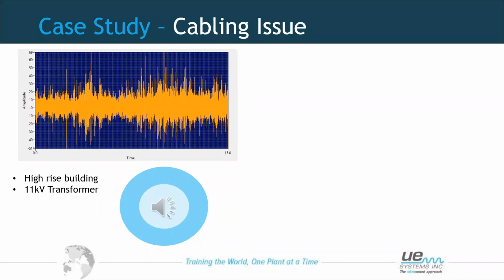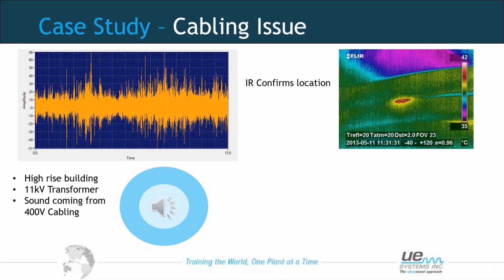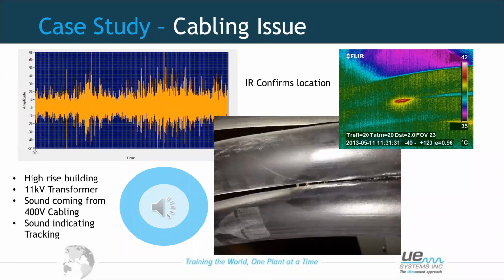So you could hear these crackling sounds that don't sound normal. And again, it was pinpointed to some cabling, where they pulled out the thermal imaging camera to confirm the source of the sound. You could then do a visual inspection and see, obviously, the heat buildup marks, identifying that there is a problem there. From the sound recording, I can tell that that is tracking occurring.